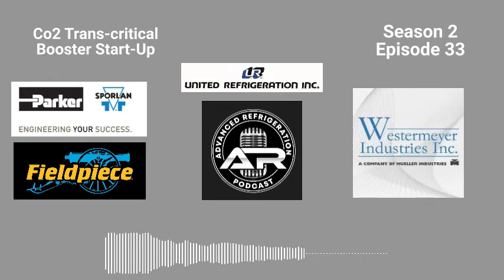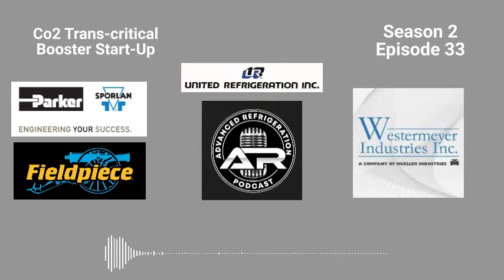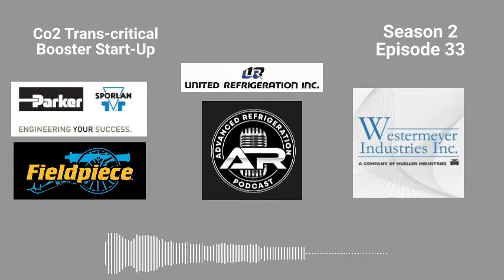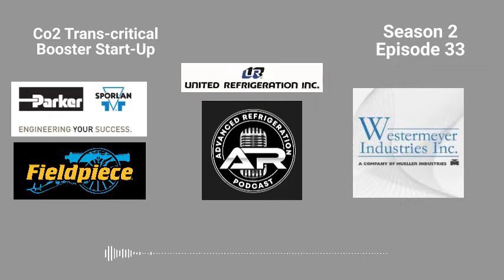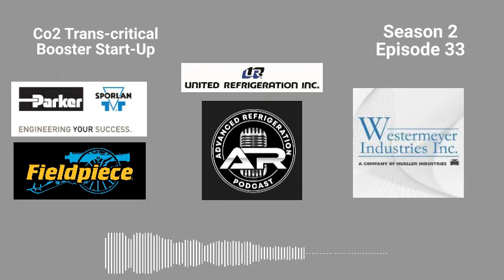So then once we go through there, you're pulling your vacuum. Now you want to start testing everything. You want to start checking pulse valves or EEVs and driving them open from the case controller, driving them closed, making sure that one's right, checking temp sensors. I do not go through the rigmarole like ice test and temp sensor, especially with Emerson stuff or Sporlan stuff. Anything with a 10,000 ohm transducer or temp sensor, especially on a case controller, I'm not wasting my time with that. They're usually accurate. So what I'm doing to test them is I will spray them with duster to make sure I have the right sensor. So I'll spray the suction temperature on the suction temperature, okay, gotcha.